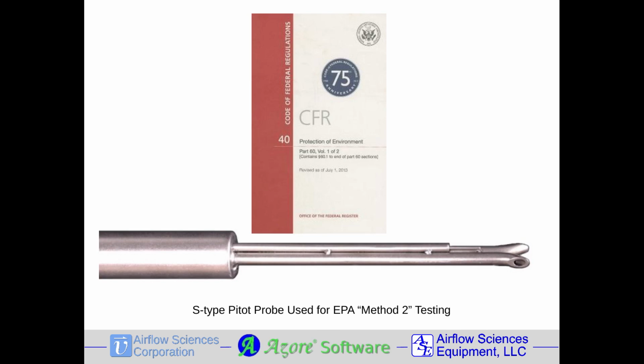If you've spent any time trying to measure the flow in an industrial application, you're no doubt familiar with the S probe. This modification of the classic L-shaped pitot-static tube has been the standard of real-world flow measurements for decades. S probes are almost bulletproof, with a simple design that's easy to manufacture, easy to use, and easy to master. With all of these factors working in its favor, it's easy to see why people tend to overlook its very real limitations.